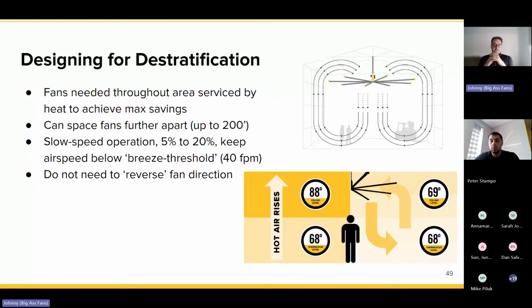That's an old adage that was based on fans that had 2 speeds in the 1980s, where basically there was no comfortable speed to run it in the forward direction in the winter, so they had to reverse it. These big fans, they're like an airfoil wing or a plane wing. Don't reverse it. They don't work well in reverse. But if you run them slow in the forward direction, you're going to achieve what you ultimately need to do.